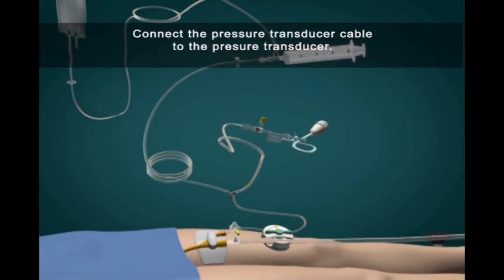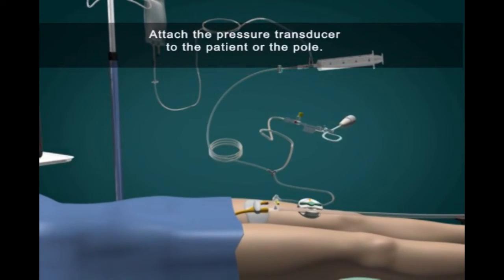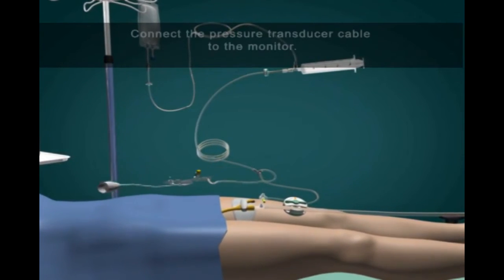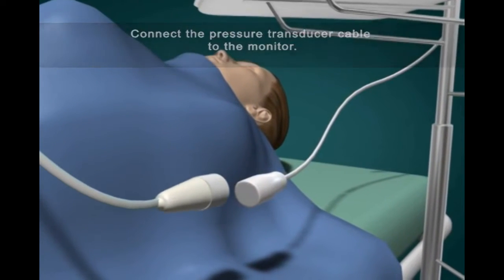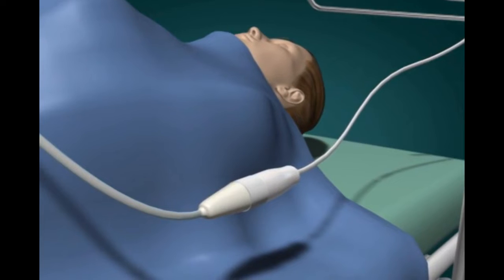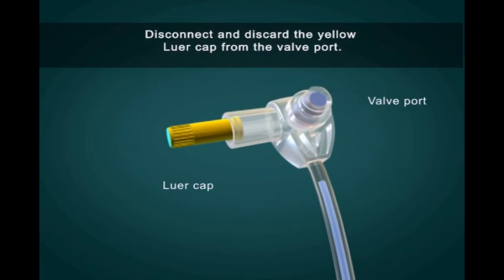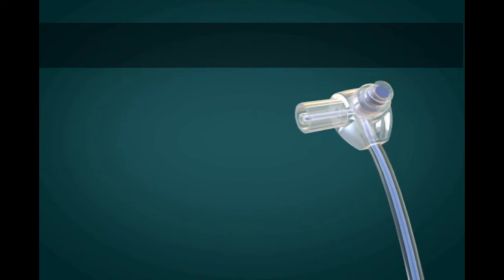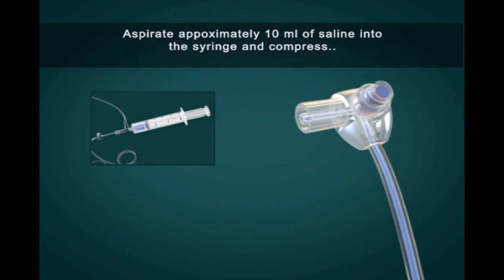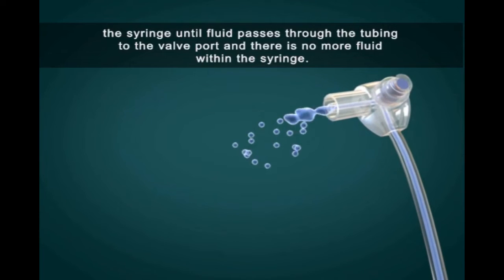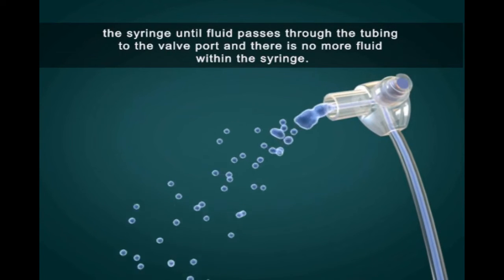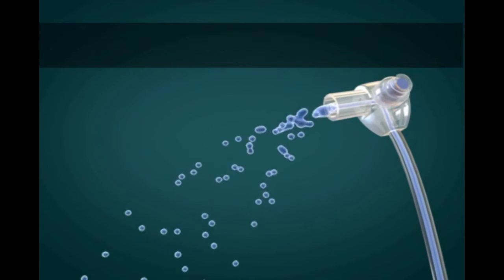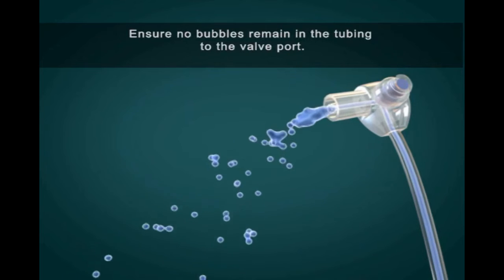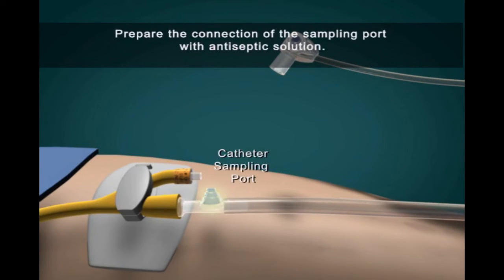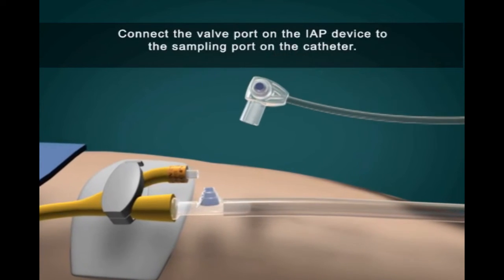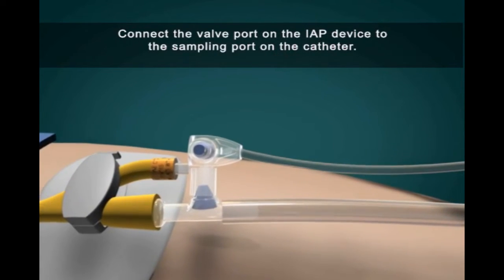Connect the pressure transducer cable to the pressure transducer. Attach the pressure transducer to the patient or the pole. Connect the pressure transducer cable to the monitor. Disconnect and discard the yellow luer cap from the valve port. Aspirate approximately 10 milliliters of saline into the syringe and compress the syringe until fluid passes through the tubing to the valve port and there is no more fluid within the syringe. Ensure no bubbles remain in the tubing to the valve port. Prepare the connection of the sampling port with antiseptic solution. Connect the valve port on the IAP device to the sampling port on the catheter.